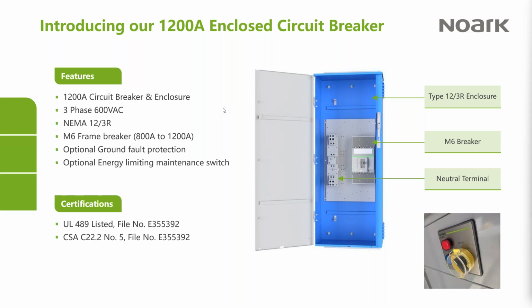As we get our feet on the ground with the Type 1, 12, and 3R, we'll probably expand that range in the future. But in the interim, we have some options where we can work with OEMs to make a customized 4X enclosure, or even in our own panel shop, we eventually will be able to do that. In terms of the 800 volt ratings, we have the 800 volt rated breakers. Those breakers in our enclosure is not part of our test program today. But again, if someone has an application for that, we'll find a way to produce it. Fantastic, thank you. Okay.